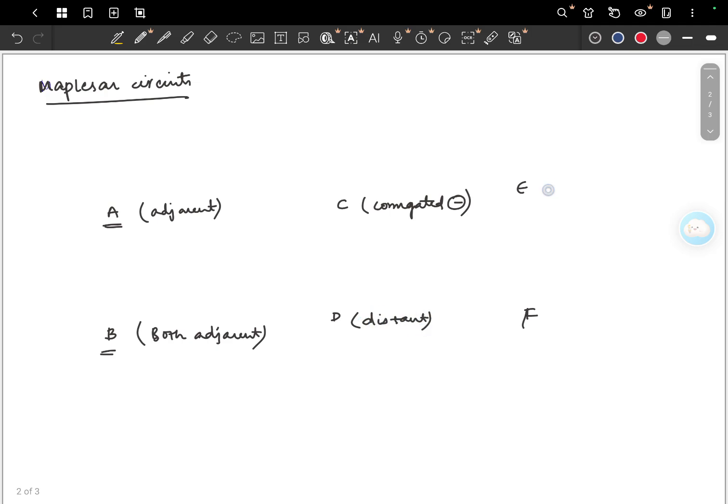In F and E you should remember that there is no APL valve. Both of these are used in children. And in E you will have no reservoir also. This is one difference between E and F. So F is more preferred than E in children.